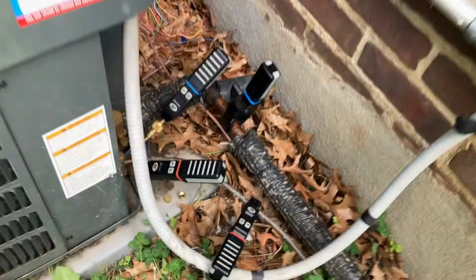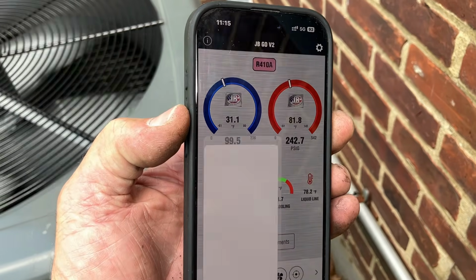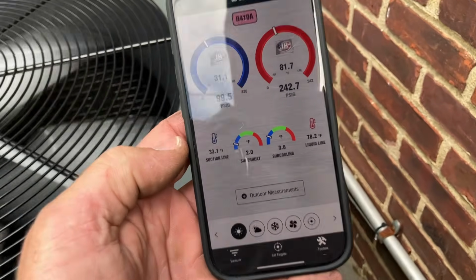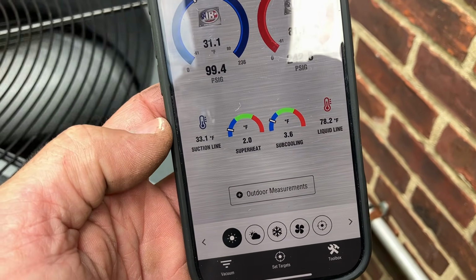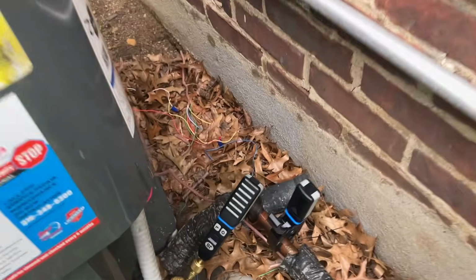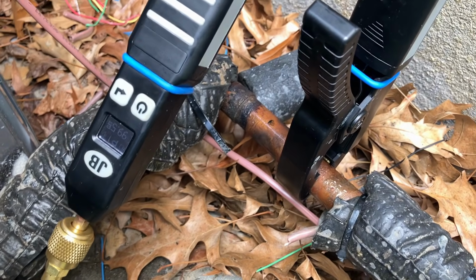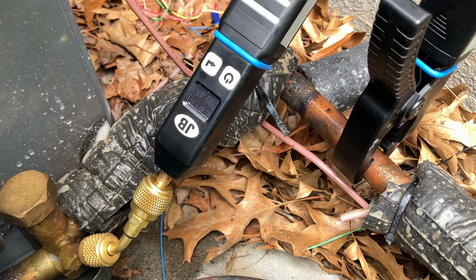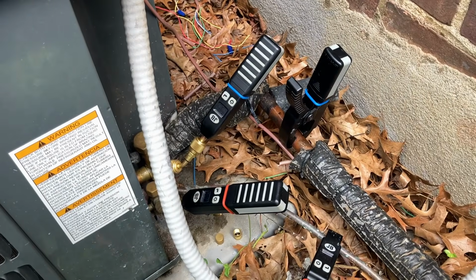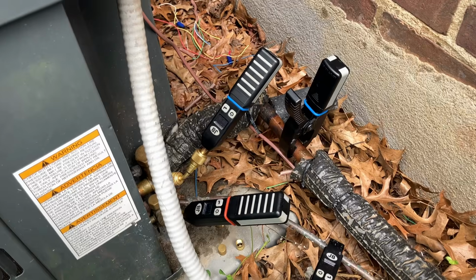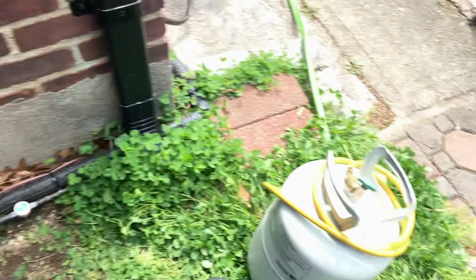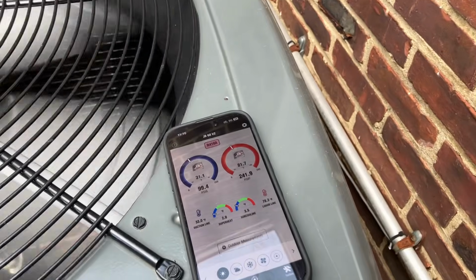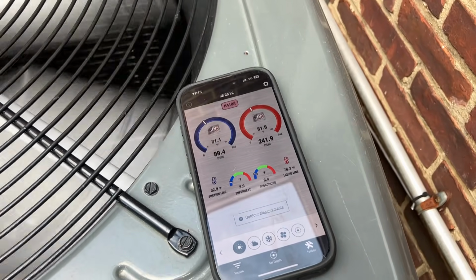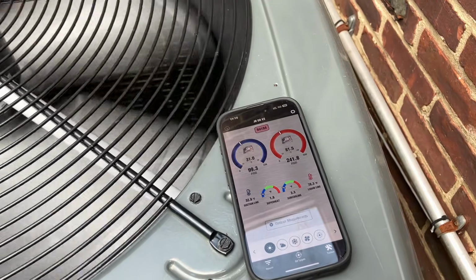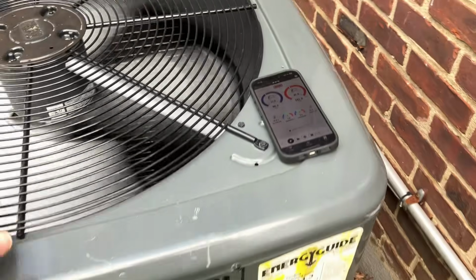We're undercharged. All right, I'm going to screenshot this before picture with 3.6 degrees of subcooling. My line is condensing. It's wet and it's beer can cold, but it is not properly cooling. So we're going to add some refrigerant. I got my 410A. I got my scale. I'm going to guess probably around 2 pounds. Factoring in the 7/8 line and the 4-ton system when it should be a 2.5-ton system.